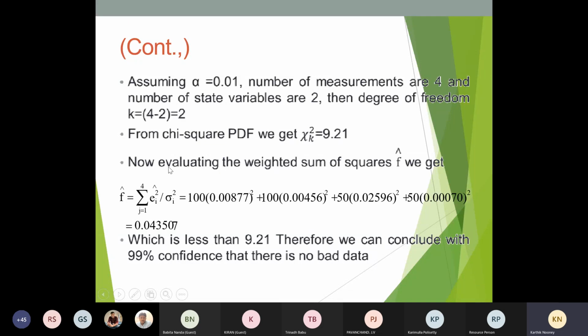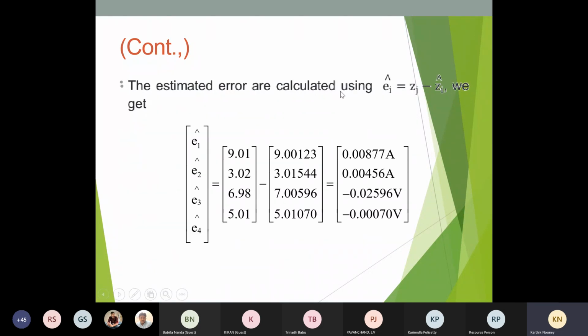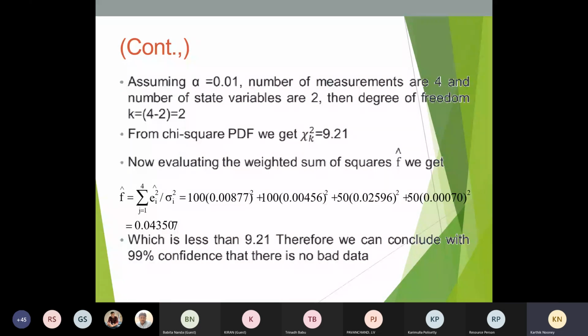Then from this, we are evaluating the weighted sum of squares. F is Ei square into 1 by sigma i square. I have said already that 1 by sigma i square is nothing but this weighted matrix. So 100 into these errors, 0.00877. It is a tedious mathematical process every time in power systems. 100 into 0.008, all the equations I have written, and if you solve that, we get F cap equal to 0.043507. See, this value is less than 9.21, whatever tolerance we have got from the table. So we can conclude with 99% confidence that there is no bad data here. That means the error is very minimal.